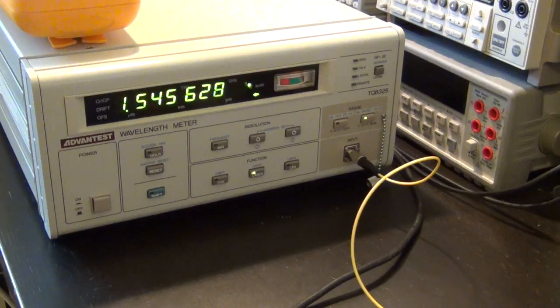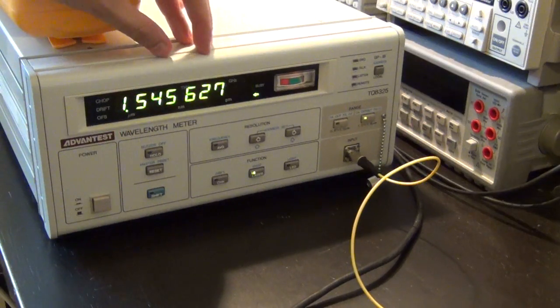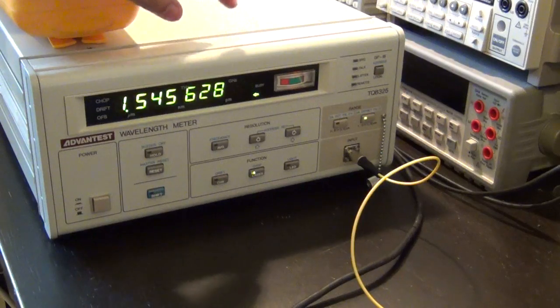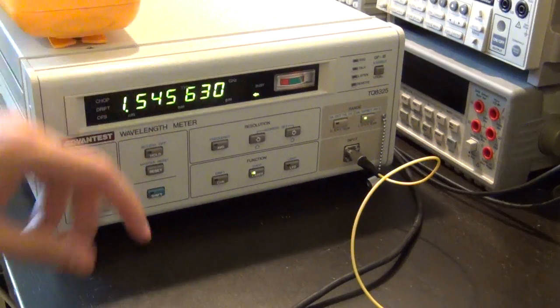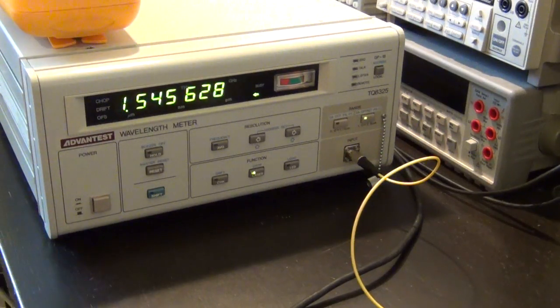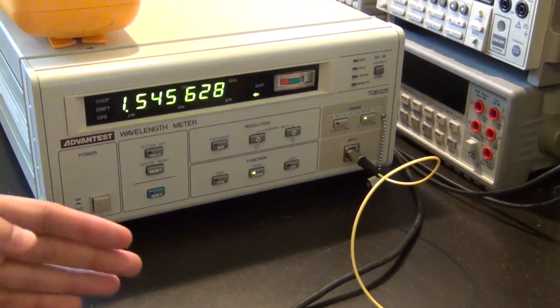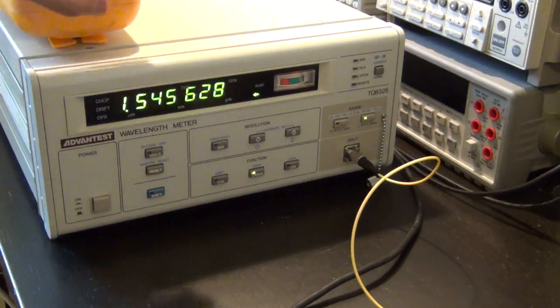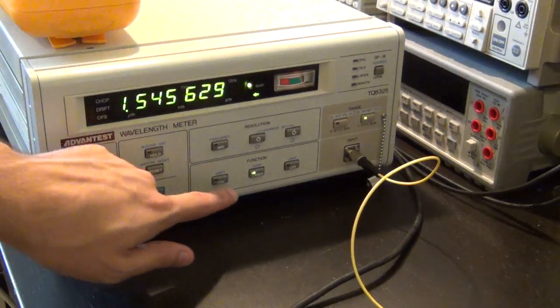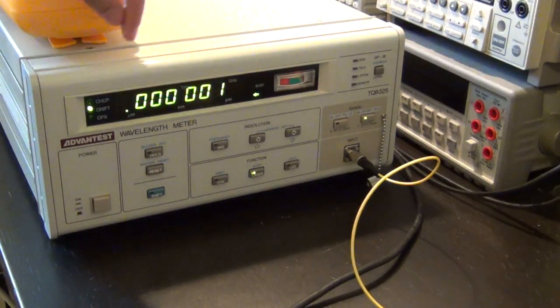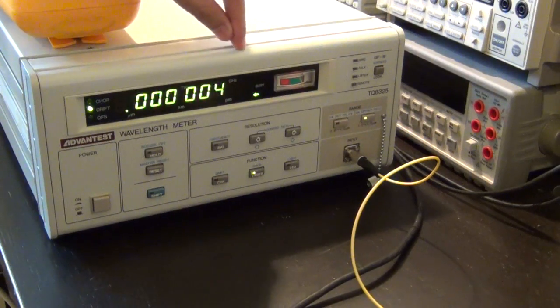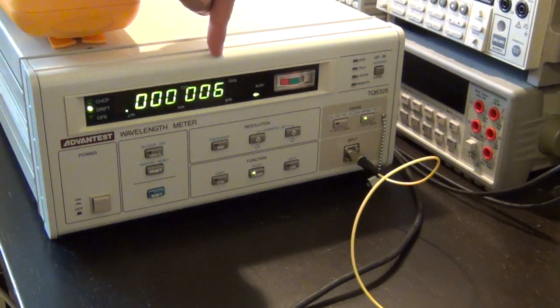Okay, so I waited a little bit. Now the wavelength seems to be fairly stable. So what I'm going to do is make a relative measurement. This instrument allows me to measure deviation from, or a drift from, a specific wavelength. So if I press this, and I press this, now it's measuring the drift. This is now in nanometers, so you can see that it's essentially not drifting at all.